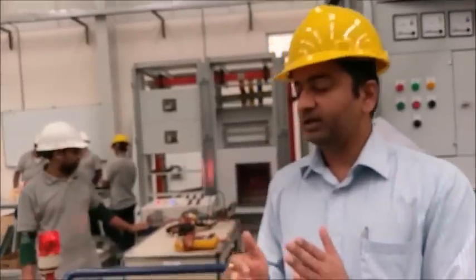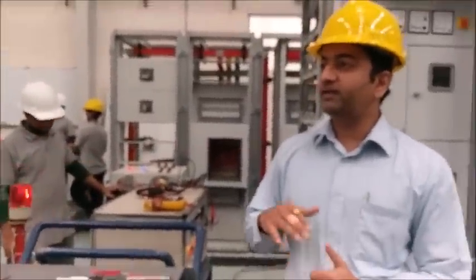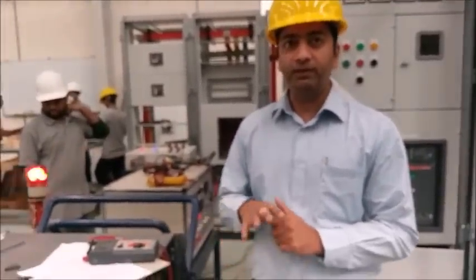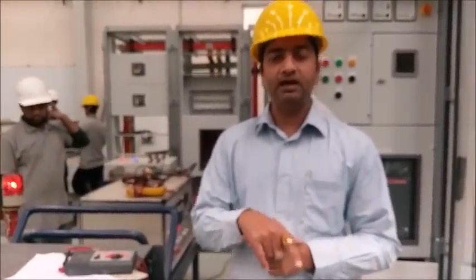Once you provide high voltage for 1 minute, if it sustains, it should sustain. After that, again you have to perform the insulation test to see that there is no breakage, because after the high voltage is applied, it will be a re-verification of the insulation. And it is recommended by IEC. So we have to perform it before the power frequency test and after the power frequency test.